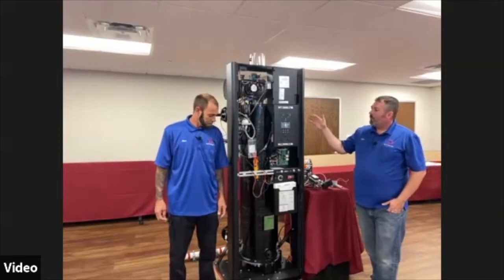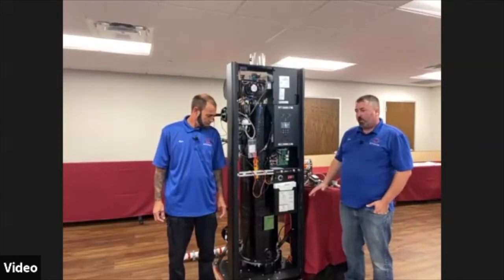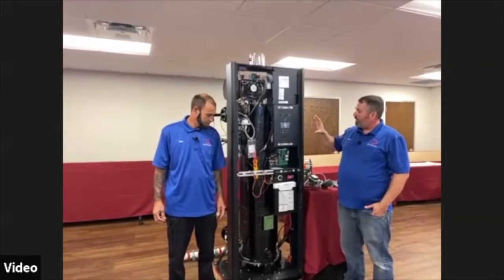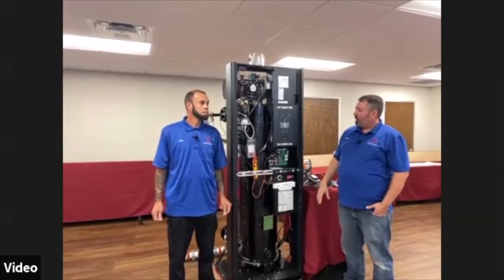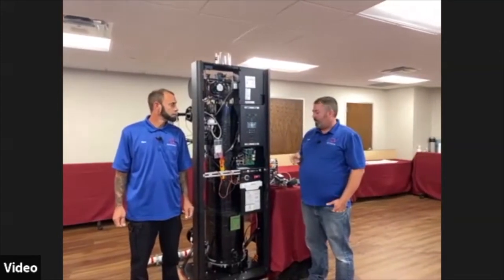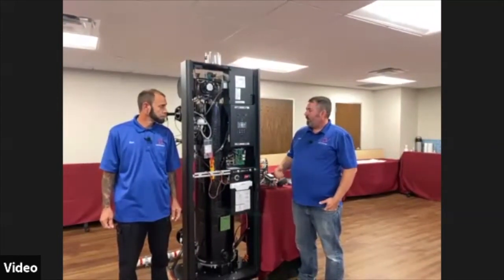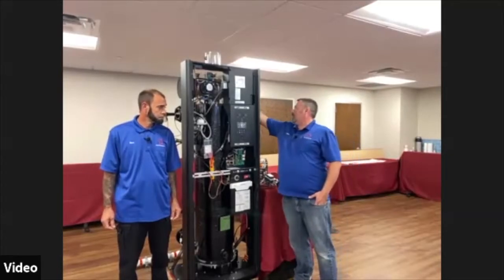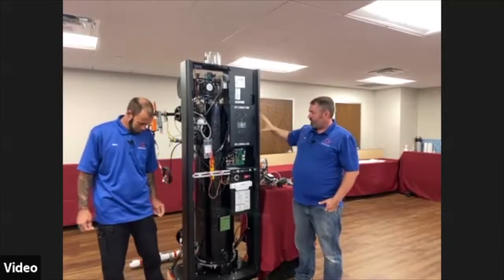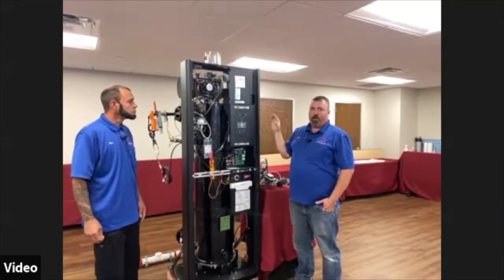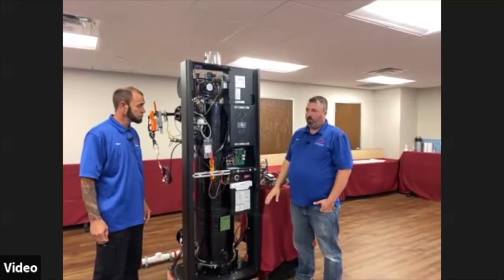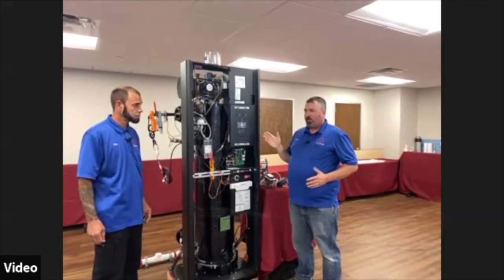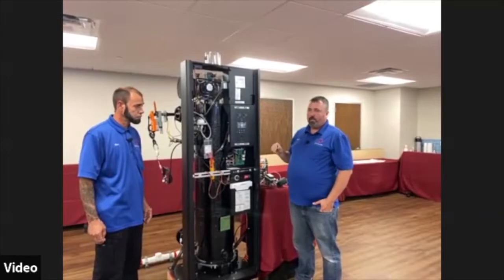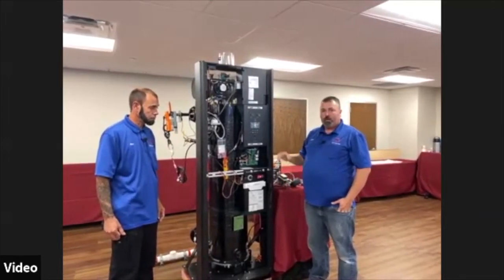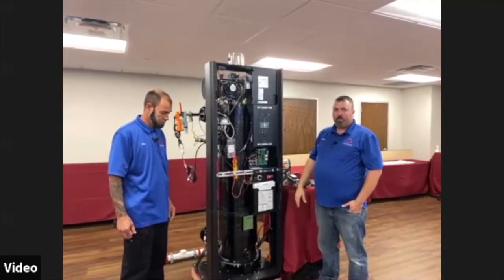No, take it. The Benchmark Platinum actually has a slightly different version of the Edge controller. There are 3 different things that the Platinum can do that the standard does not. It runs an O2 trim system. What that'll do is take the reading of this O2 sensor, which on the standard is just for read only. But on the Platinum, it'll read that O2 sensor and self-calibrate the boiler daily based on conditions of how dirty your filter is, how warm your inlet temperatures are. It'll keep your boiler running at premium efficiency every day.